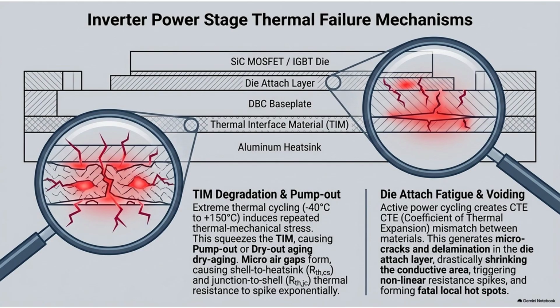When the air replaces the TIM, you see an exponential, incredibly dangerous spike in thermal resistance. Heat transfer just plummets. So the heat gets trapped. It hits a wall of air and has nowhere to go, so the temperature inside the chip skyrockets. Which perfectly sets up the second horseman of thermal failure, which is die-attach fatigue. And this one is also rooted in that same physics concept, things expanding at different rates.